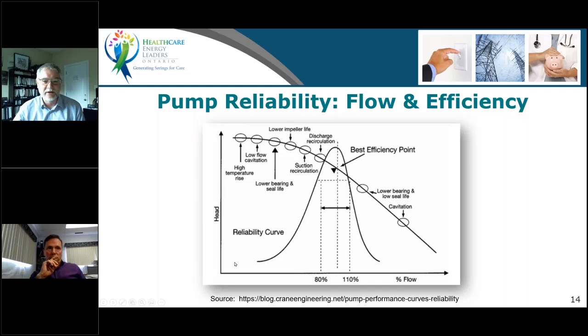So here's your head and here's your flow, and here's your pump curve moving across like it does. This is their best efficiency point, but now they plot the reliability curve on this. They show that as you move away from the best efficiency point, to those egg-shaped circles that are lower in efficiency, things are happening. You get things that will reduce the life of the impeller, like cavitation, and if it's really badly throttled, you'll end up creating high temperature rise because the pump can't even cool itself. The same thing goes if you move the pump to the other end of the curve too.